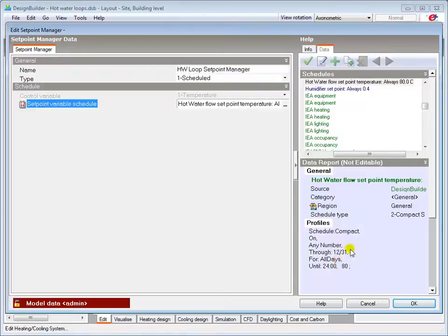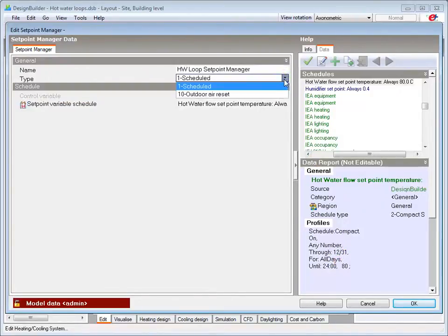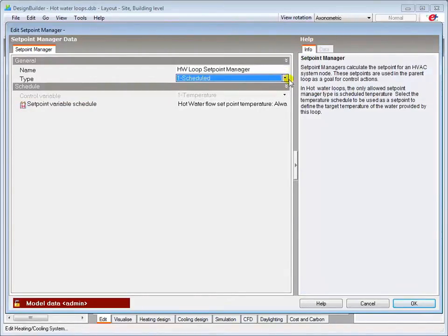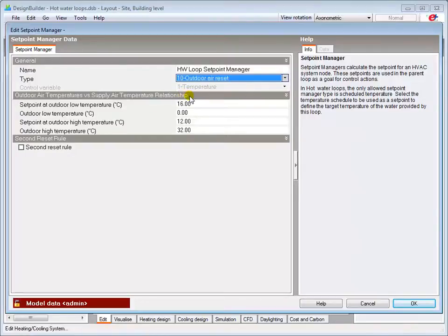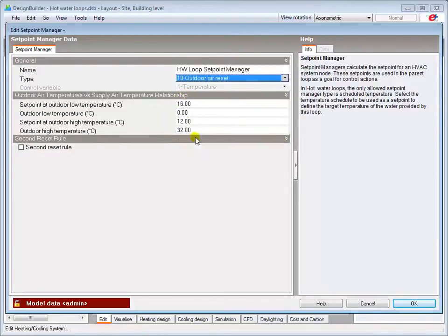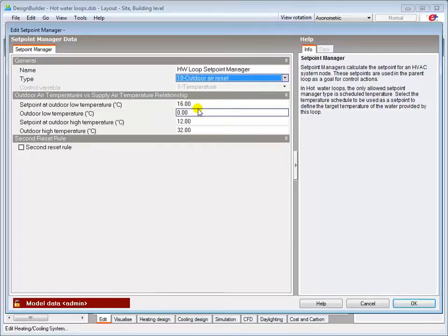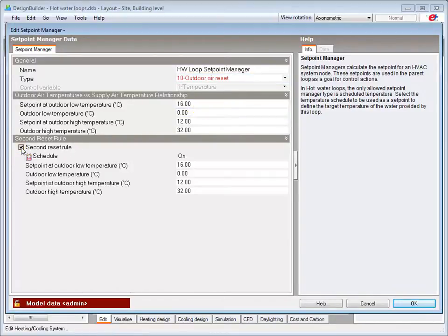You can also use the outdoor air reset option to simulate the effect of varying the flow temperature setpoint between the defined upper and lower outdoor air temperatures if your building has weather compensation controls. The second reset rule allows you to schedule another rule for specific periods, for example.